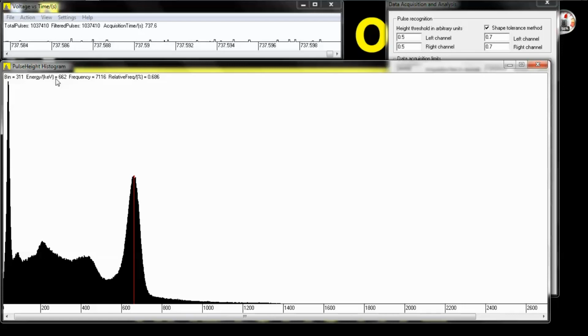See, energy. This Compton edge should be around 400 to 480, depending where I click. 430, 420, that's pretty close. This backscatter peak should be right around 220-ish. That's pretty close. We could do a lot better job of calibrating this, by the way, and I'll go into that in a video where I go more in depth about isotope detection, where you need to get really, really good with your calibrations. But I'm showing you the basics right this moment.